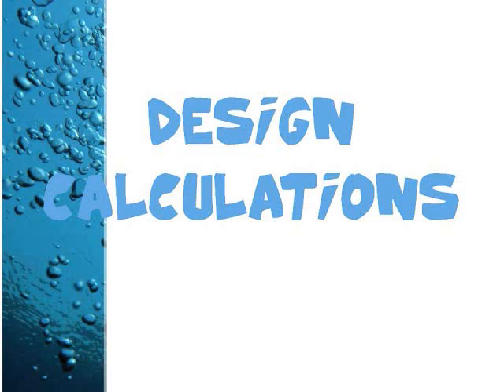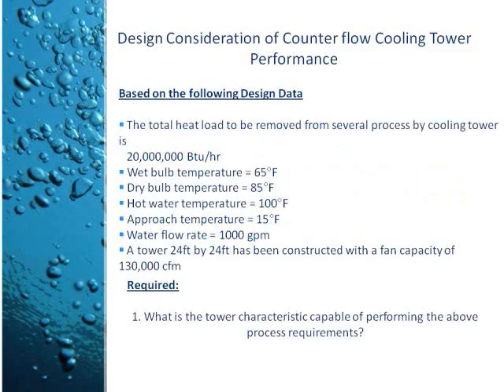But first, we will test its efficiency by solving problems using numerical integration and the Chebyshev method. We are given with the following process requirements. First is the total heat load to be removed from several processes by the cooling tower, which is 20 million BTU per hour. The wet bulb temperature is 65 degrees Fahrenheit, which is the non-equilibrium temperature at which a small amount of water comes into contact with a continuous stream of gas. The dry bulb temperature, or the actual gas temperature, is 85 degrees Fahrenheit, and the hot water temperature is 100 degrees Fahrenheit.